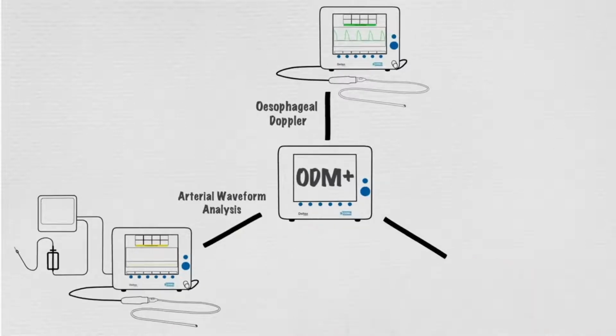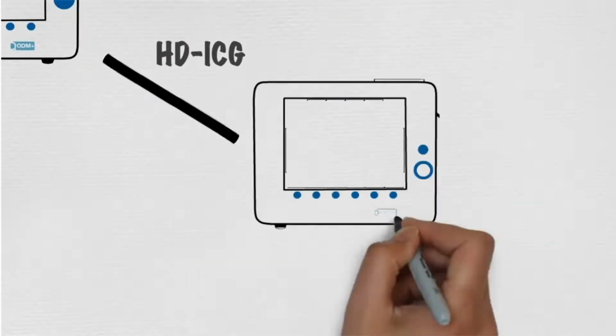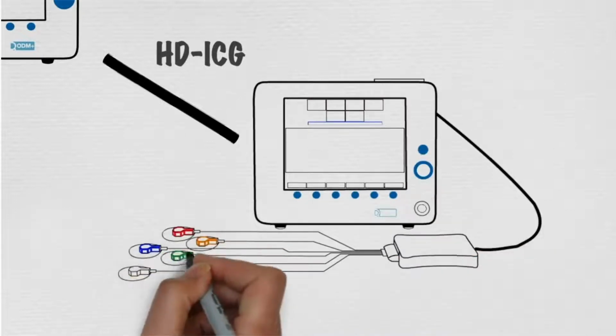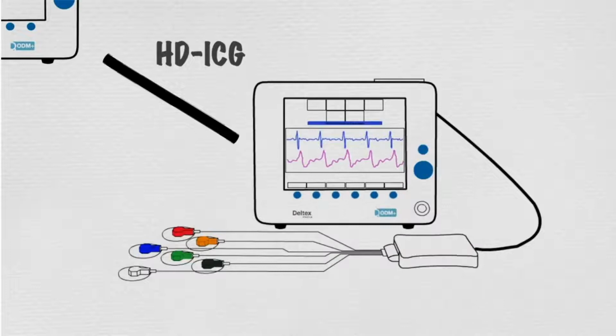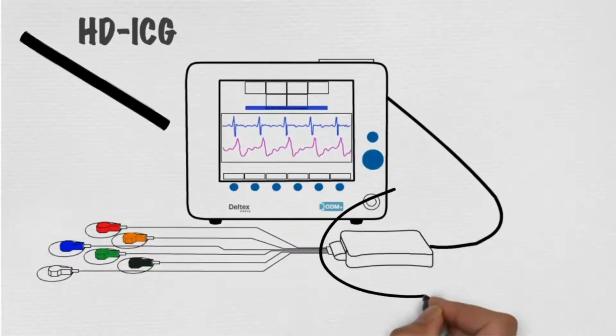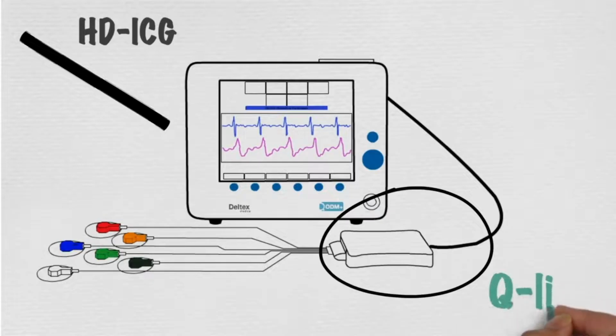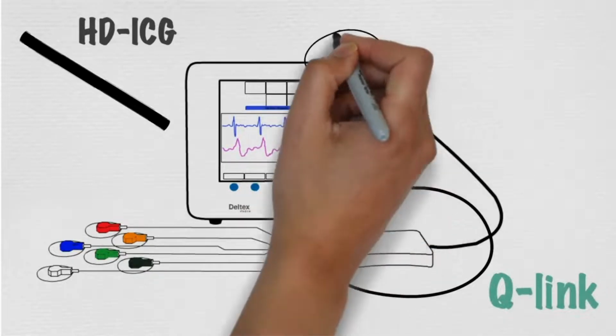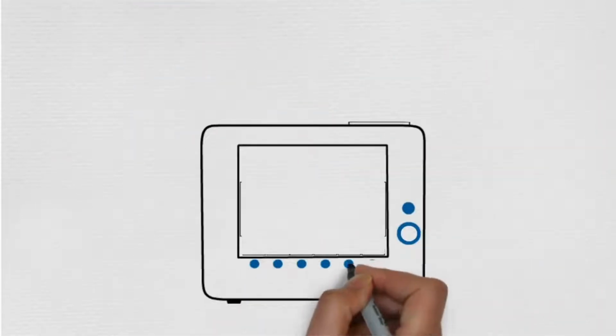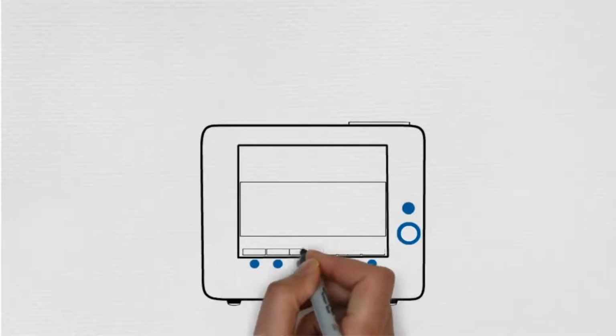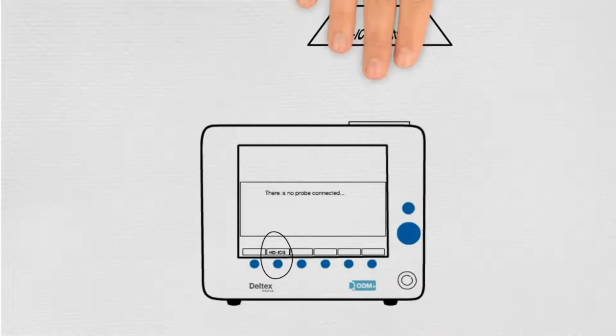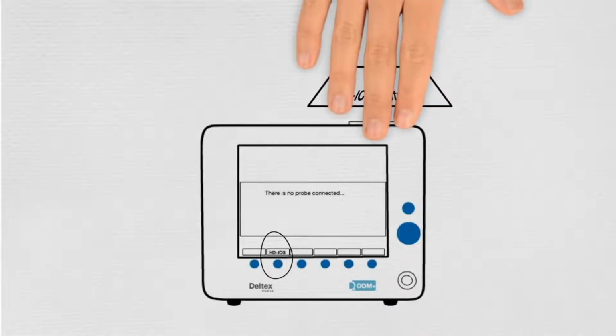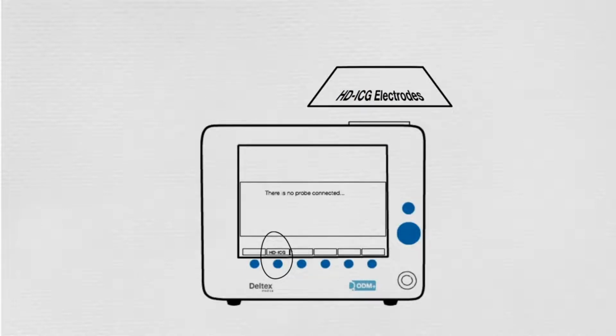And now high-definition impedance cardiography, a completely non-invasive technology suitable for monitoring awake and lower-risk patients. HD-ICG is incorporated into the ODM Plus via the Q-Link interface box, connected via the USB hub. From the no-probe connected screen on the ODM Plus, simply press the HD-ICG button to enable monitoring. The electrode packet contains an RFID tag, which when placed briefly on the USB hub, provides 24 hours of patient monitoring.